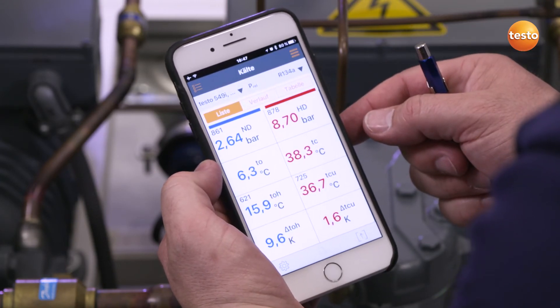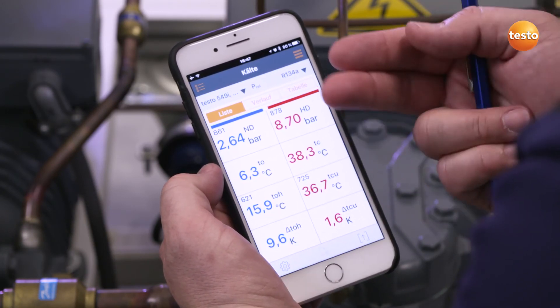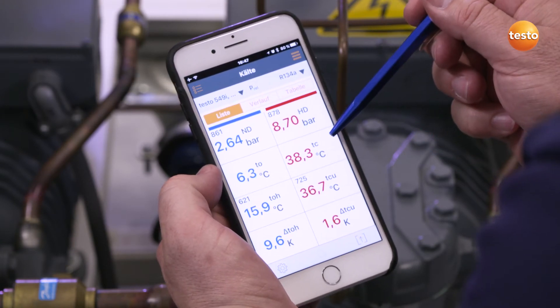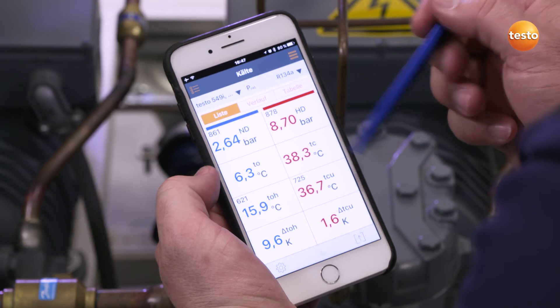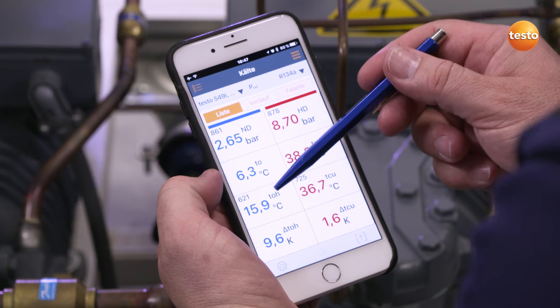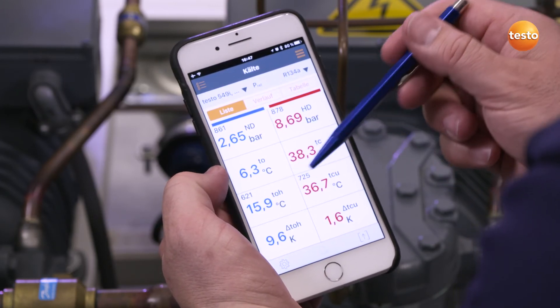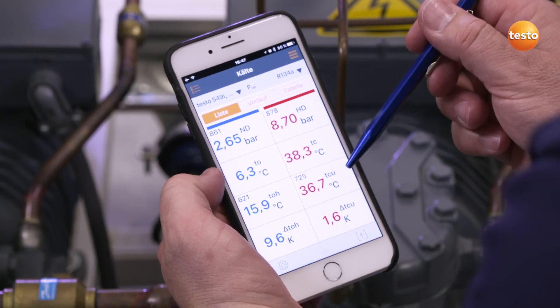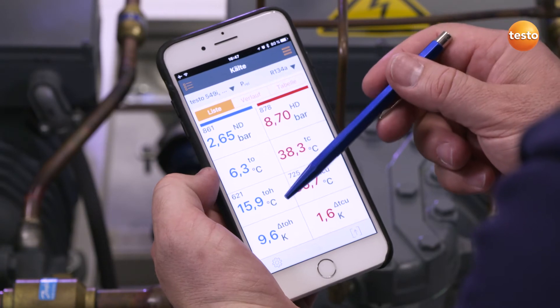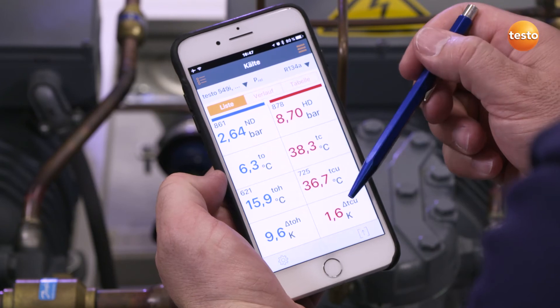The high pressure probe reports a pressure of 8.7 bar, and the low pressure probe 2.6 bar. The instrument automatically converts the respective evaporation and condensation temperatures, which we are then able to read directly. Both temperature probes report a temperature of 15.9 degrees Celsius at the evaporator outlet and 36.7 degrees Celsius in the liquid line. The corresponding evaporator superheating is also generated here automatically — in our case, 9.6 Kelvin is indicated — and a subcooling of the liquid line of 1.6 Kelvin.